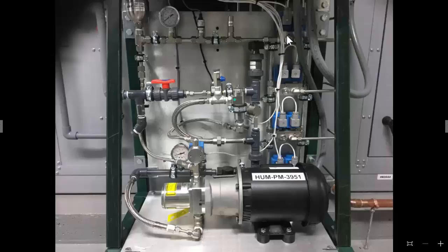And then we have the zone solenoids over here. There are 4 zones, and each one of these zone solenoids actually has 2 coils on it, and then each line goes out into the air handler, being a different zone and a different amount of nozzles on each zone. And I cover that in a separate video. The connections to these zone valves are NPT, National Pipe Thread, 3/8 inch, and there's a connection on each side, and then there's a connection out the front. The connection on this left side is the input water going into it. The connection out the front is each zone going to the nozzles themselves in the air handler, and the connection out the other side is the dump valve, or the dump portion of the valve, and that is right here.